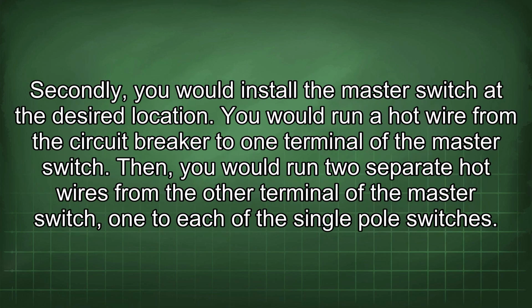Secondly, you would install the master switch at the desired location. You would run a hot wire from the circuit breaker to one terminal of the master switch. Then, you would run two separate hot wires from the other terminal of the master switch, one to each of the single-pole switches.